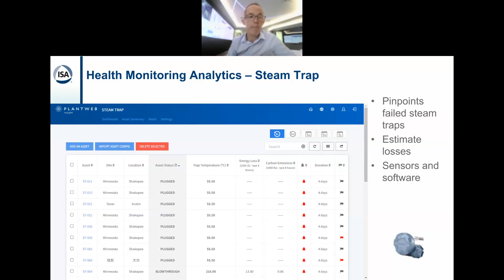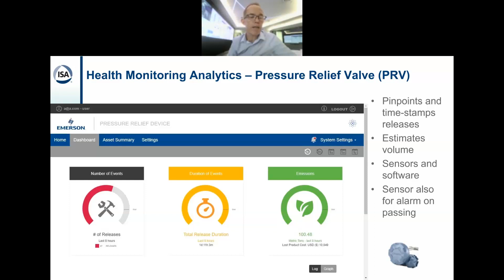Similarly, the recommendation is to automate PRV monitoring with sensors and software. So you get a positive timestamp indication of when the release occurred and for how long, estimated release amount, and you know exactly which PRV is passing or releasing. And you can correlate the release to the process event leading up to the release, so you can make changes to prevent reoccurrence. That is, this is a flare reduction. It's also helpful for reporting. When passing is detected by the sensor, you can overhaul sooner, thus minimizing product loss and flaring to become more sustainable.